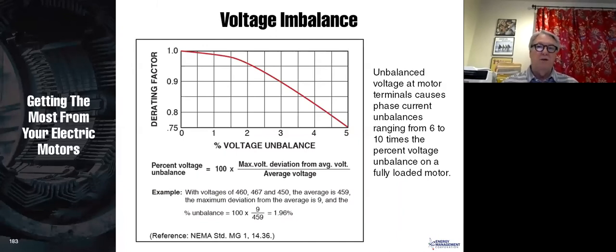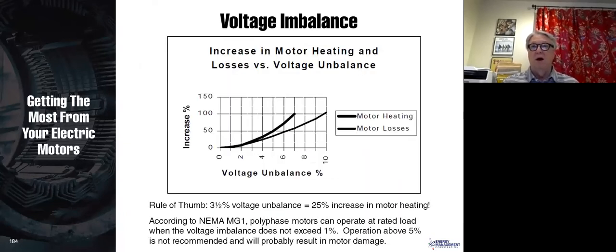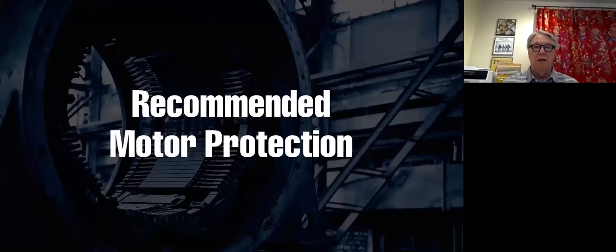Voltage unbalance: 3.5% voltage unbalance can cause 25% additional motor heating. So that's certainly something that can cause a hotter running motor. And here's some graphs that show you voltage unbalance.